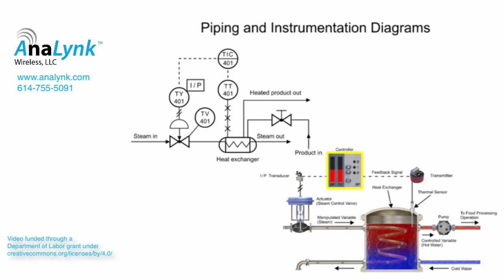The controller and indicator is the instrument where the transmitter sends an electrical signal, shown in the functional identifier as the second and third letters, I and C. Balloons with a solid dividing line indicate that the instrument is board mounted.